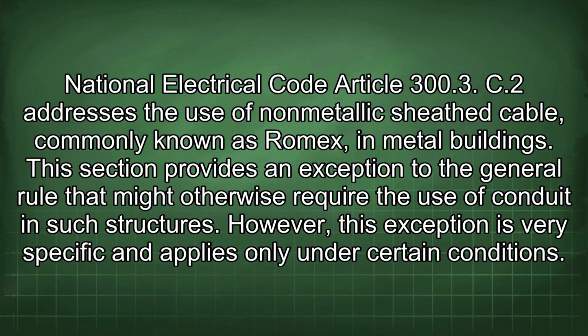National Electrical Code Article 300.3 C2 addresses the use of non-metallic sheathed cable, commonly known as Romex, in metal buildings. This section provides an exception to the general rule that might otherwise require the use of conduit in such structures. However, this exception is very specific and applies only under certain conditions.